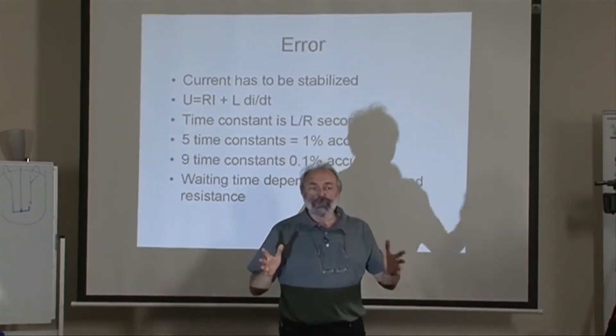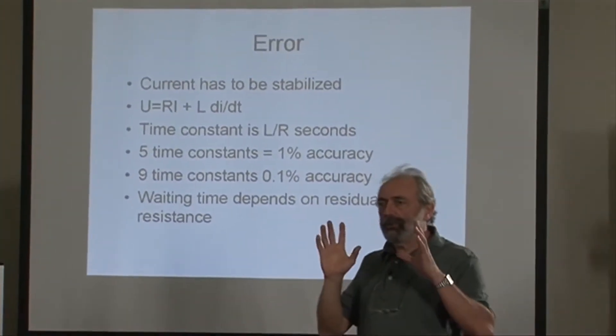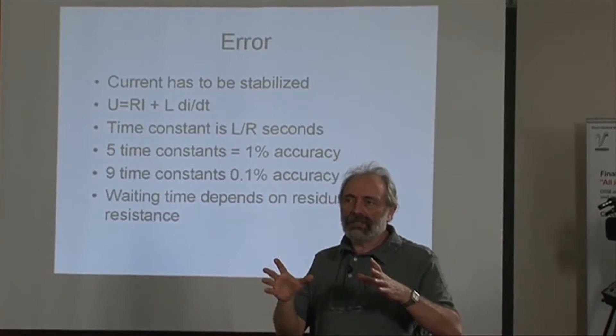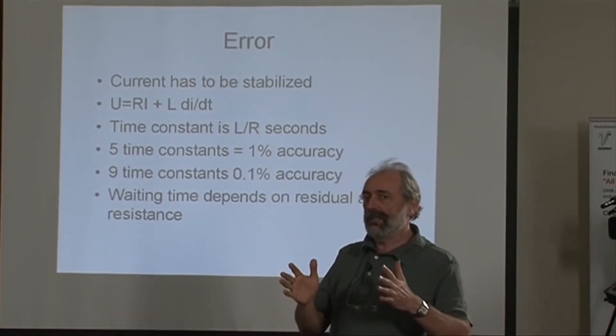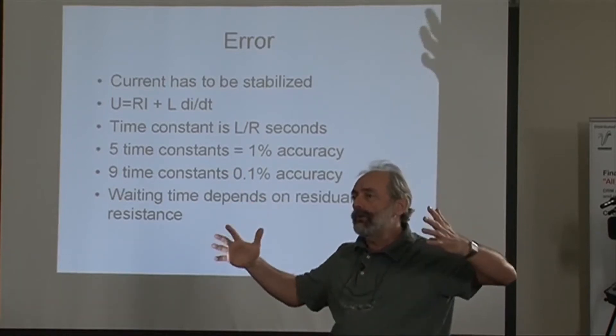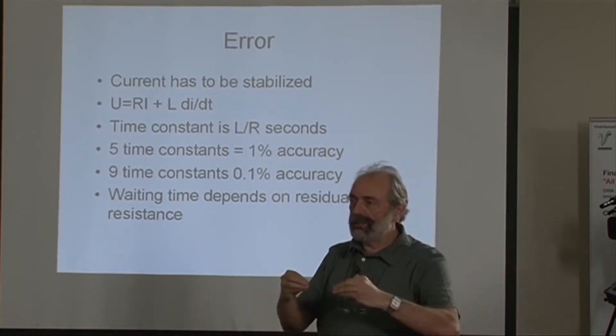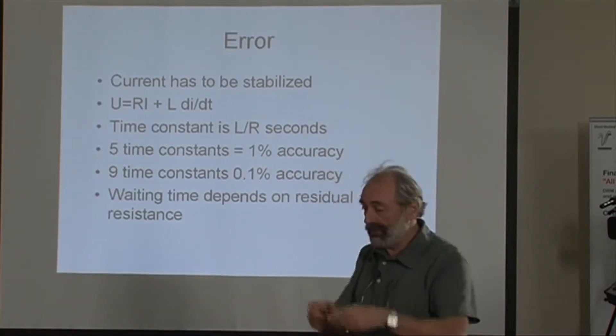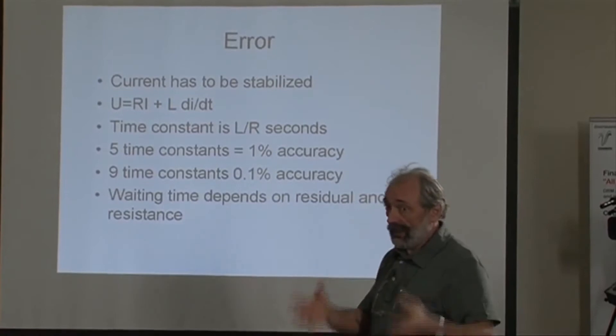I cannot change the R. Yes, I can. I can probably do with different cables, different instruments, introduce resistance. But the problem is if I introduce resistance, then I need more power. So I'd like to minimize my cable resistance, so the instrument measures the transformer, not the cables.